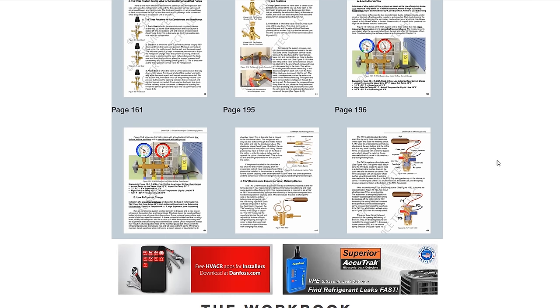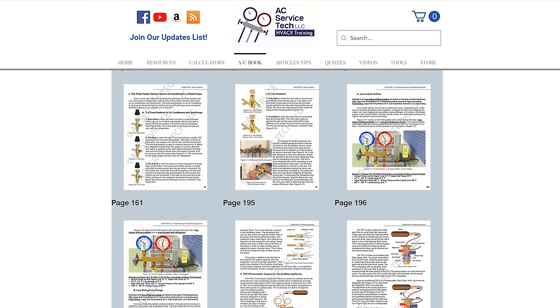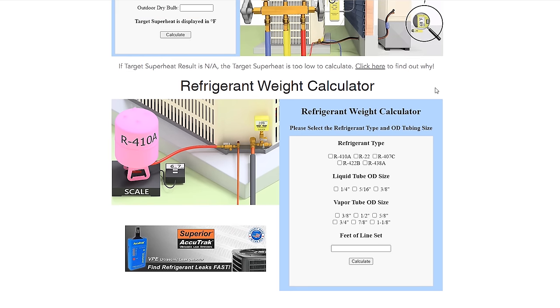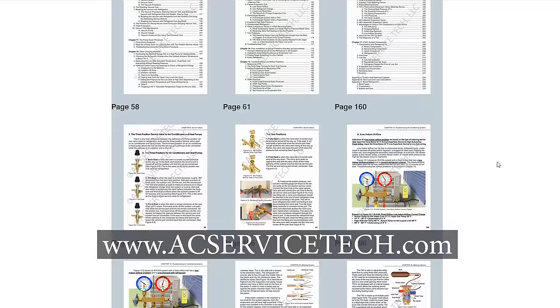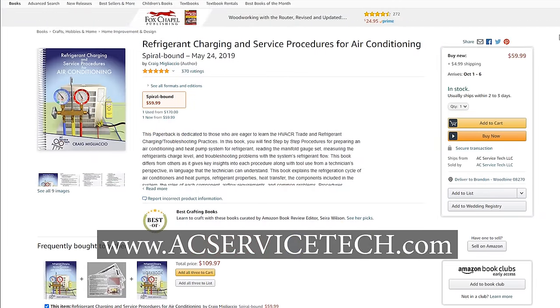In the middle of winter if you do a heat pump, you'll need to weigh in the correct amount of refrigerant so the system runs accurately — you do that by the line set length, weighing in a certain amount of ounces per lineal foot. You can check out the full outline and sample pages at acservicetech.com/acbook. We also have our physical products such as a thousand-question workbook and quick reference cards available on Amazon. Hope you enjoyed yourself and we'll see you next time at AC Service Tech Channel.